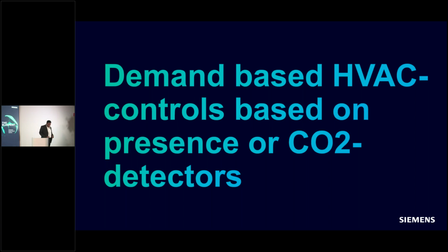Now I'll move to the next part of the presentation, demand-based HVAC controls. The same sensor is used here for total room automation. Lighting and HVAC are very correlated; they go hand in hand. In a conventional system, you have a separate controller for lighting and another for HVAC. What are the drawbacks of such independent systems? There needs to be intelligence where both talk to each other, and that is the real concept of total room automation.